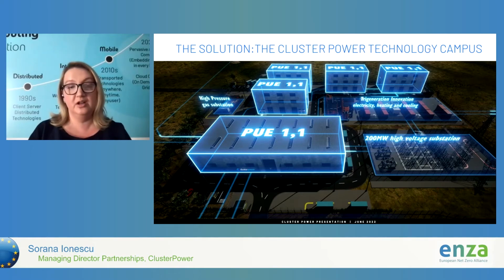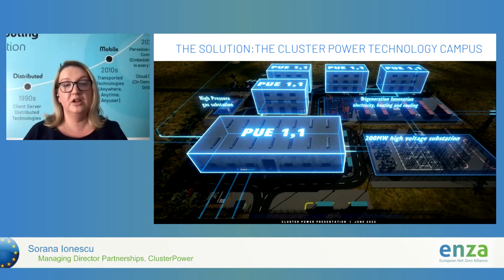This equipment requires a very stable environment, so it's really important to maintain temperature and humidity properly inside, and to have a reliable source of energy. We are using this tri-generation innovation as a primary source of power, and as far as we know, this has not been done in the industry before as a primary power source. Of course, we have a secondary and tertiary source of power too, because we are a tier 3 data center - we need to be as redundant and resilient as possible.